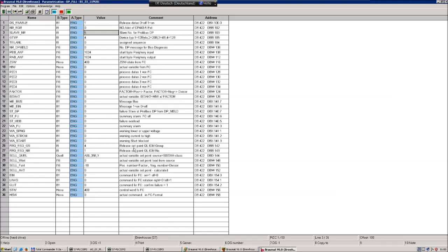And then also an ICM. We need to define the ICM, to which ICM number it is linked. You input it in here, and then when this is activated and you give a set point, the Danfoss will start up. And there are some feedbacks in here to give you information about the status of the motor, whether it's broken down or something else. You get it from here. So in this way, you can very easily manage VSD, variable speed drives.